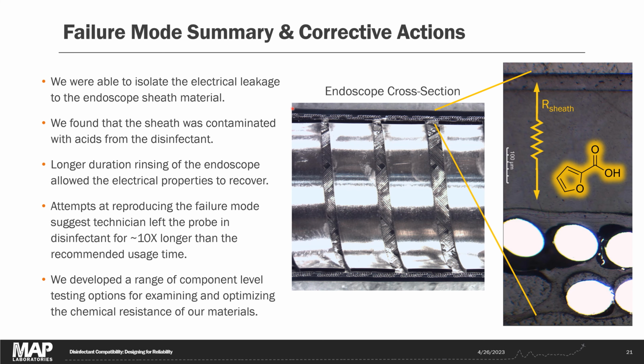In summary, we were able to isolate the electrical leakage to the endoscope sheath material. We found that the sheath material was contaminated with acids from the disinfectant. We found that if we rinsed the endoscope in water, we were able to extract those acids and the electrical properties recovered. We were then able to pass the electrical leakage test. And when we tried to expose the endoscope to disinfectant to reproduce the failure, we found that it took about an hour for us to fail the electrical leakage test. And then most importantly, we developed a range of component level testing options that allow us to examine our different candidate materials and our different disinfectants and evaluate if something's going to be a problem before we have to go about building a $10,000 plus device.